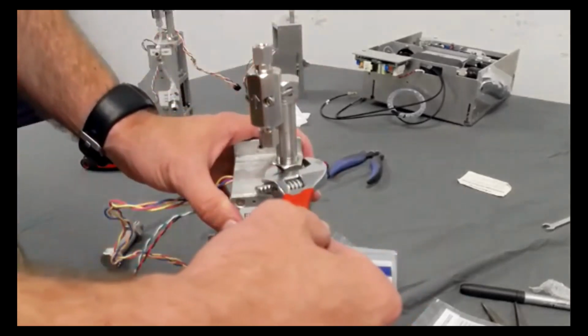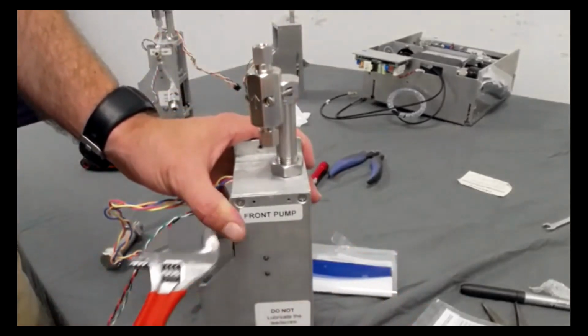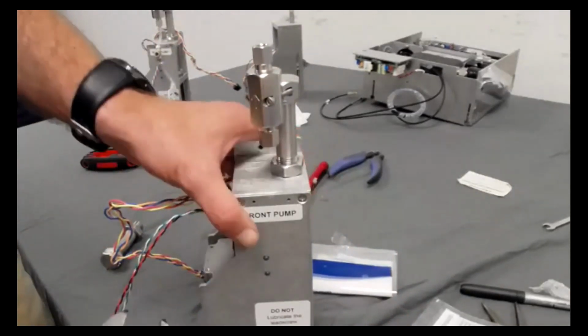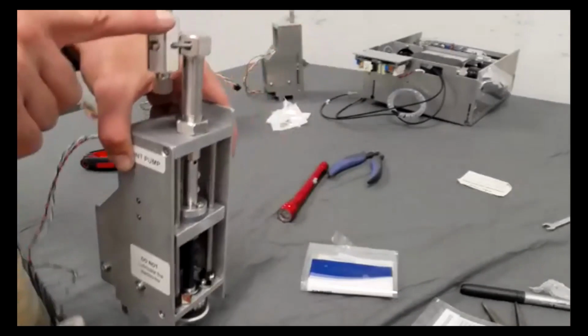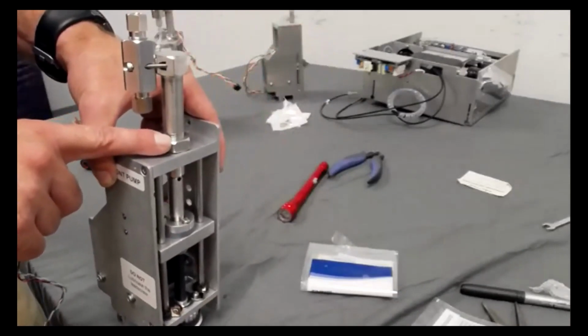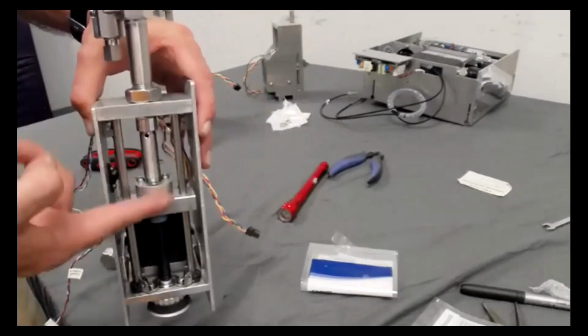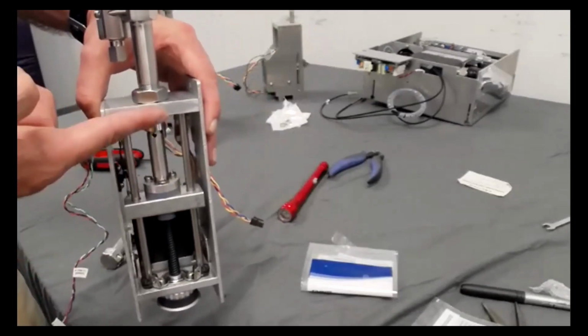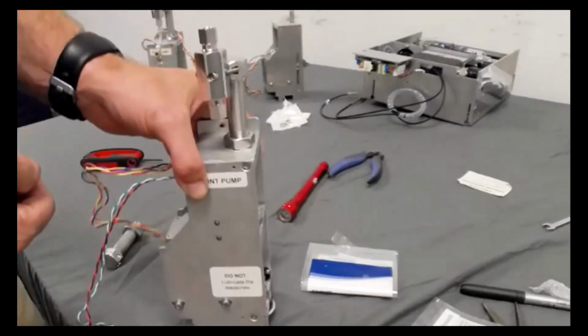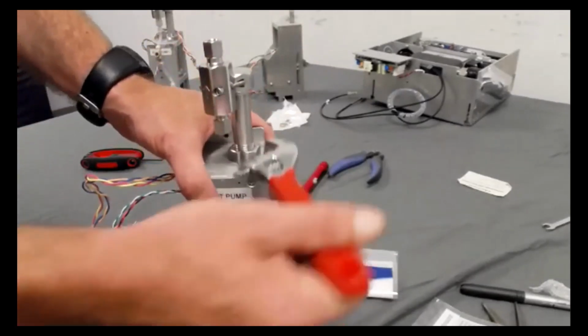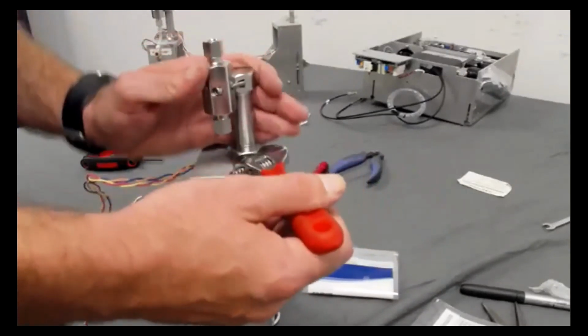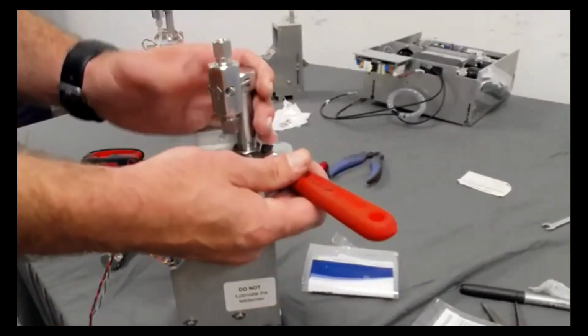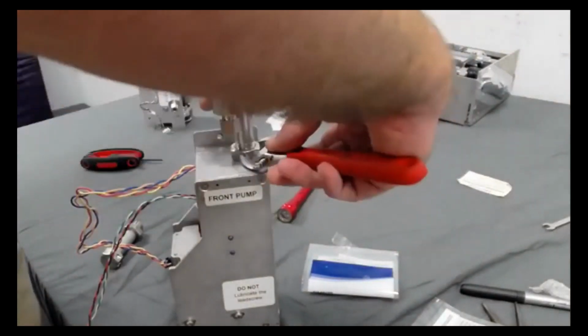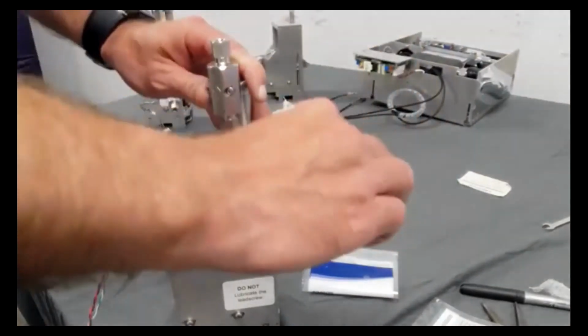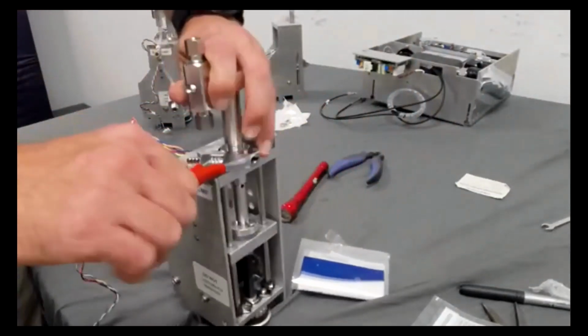Judd, will that screw down any further if the piston's wound down a little? Yes. If your piston is all the way down, you can screw it past the point where I have it. So that's a critical step for me anyway, to move this to the top of its travel. Thanks. Yeah, no problem. So now I'm going to finish tightening this down with my wrench. I don't want the cylinder to move, so if it does, move it back before you do your final tighten. If you do this final tighten and it moves the cylinder, just loosen it and put it back, okay?